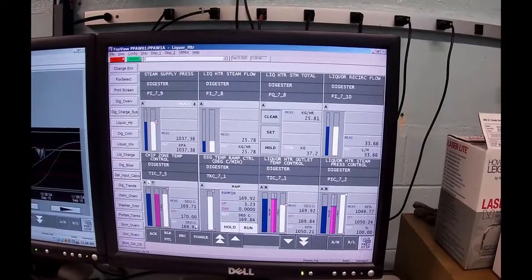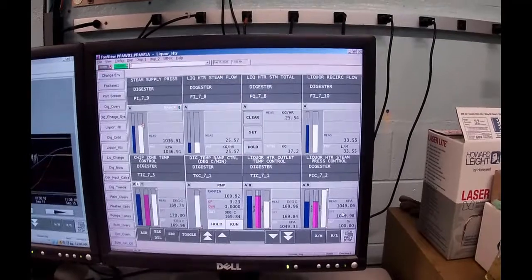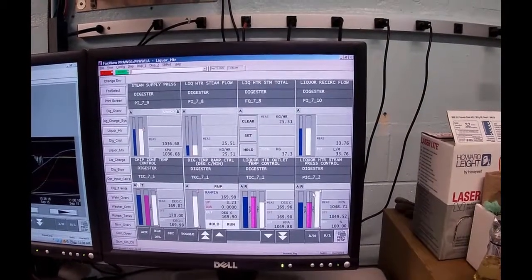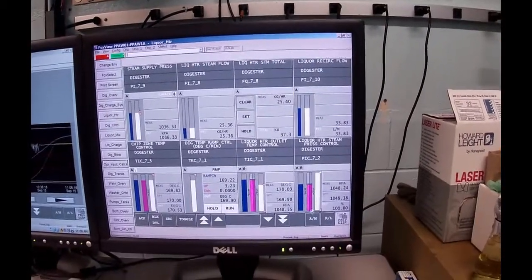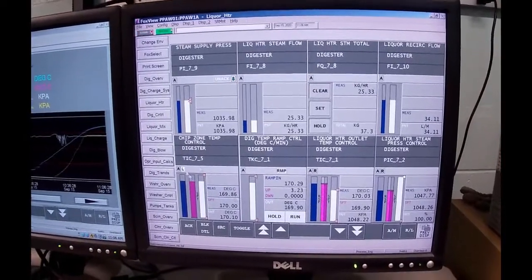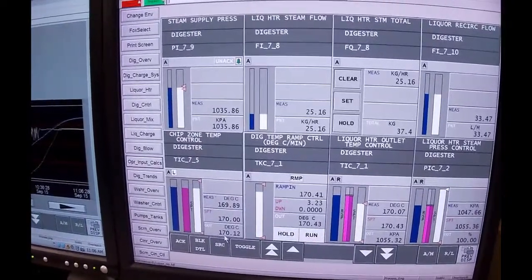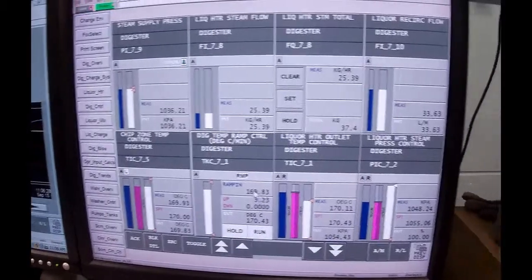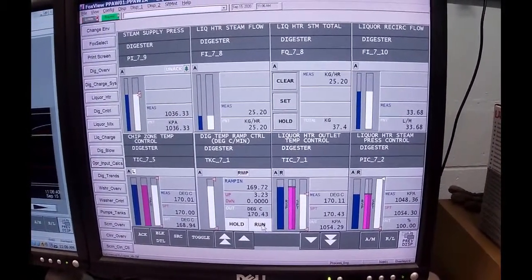And the moment the track gets released, this guy will be set pointing that guy, who will be set pointing that guy. And you'll actually, may hear, but you'll see the steam valve will throttle back. It won't be up as high as it is. We're getting close. It's 0.86. It just released. It's off this one here. So the track is now gone. This guy is now set pointing that guy, which is actually passing right through. I'm going to take this and turn it off.